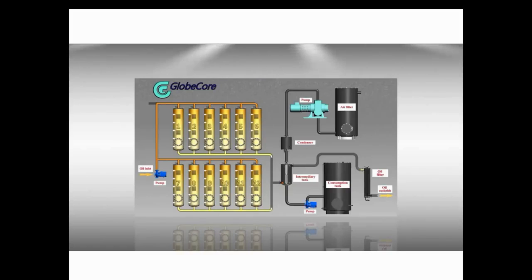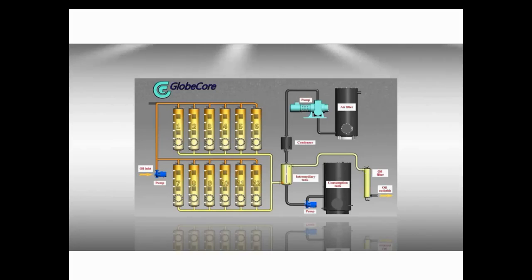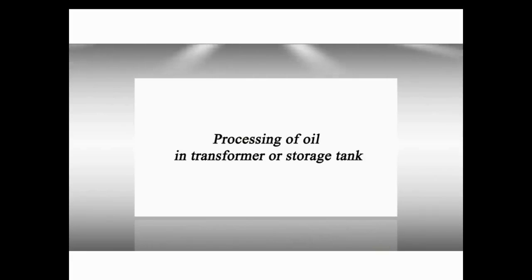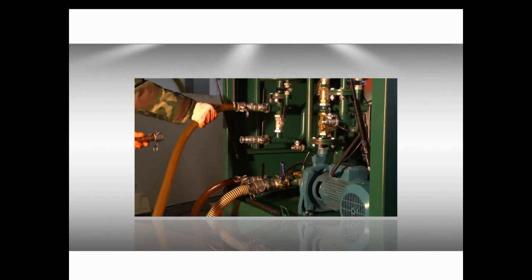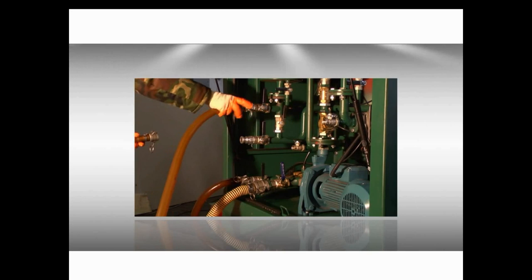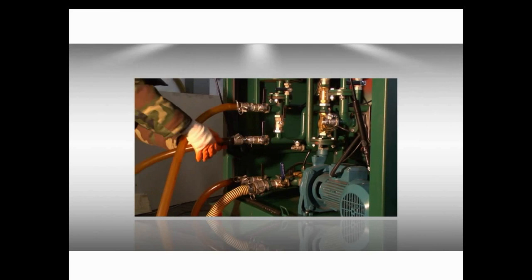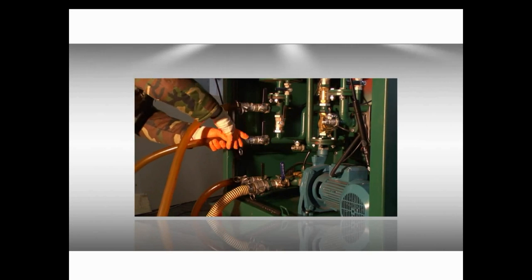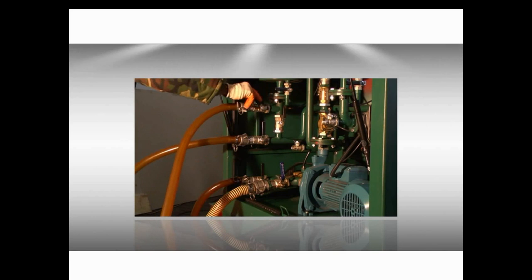Thus, it causes instability in the transformer, as oil in windings is still 0.1 acidity. So, what happens? There is automatic equilibrium between oil in windings and outside the windings, because oil outside the windings draws acidity out of the insulation.